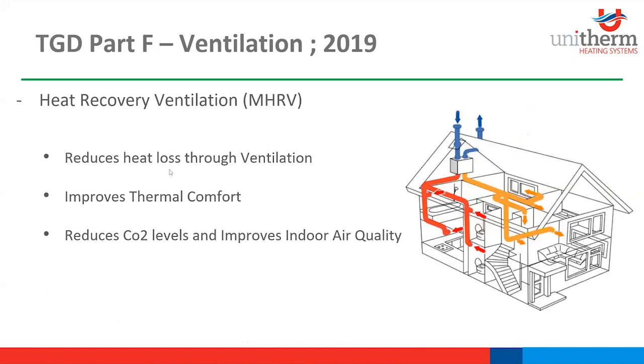So I suppose an example there, if you had warm air at 22 degrees in your kitchen, your bathrooms, your wet rooms, your utility, and cold air outside at 5 degrees, your air supply to your living rooms and bedrooms will be coming in around 18 degrees. So that's taken off the wind chill, or any kind of chill you have from dumping out warm air and bringing in cold air and putting more work on your heating system. So there's no compromise on thermal comfort there, as the fresh air is preheated through the heat exchanger before coming into the building envelope. Our systems as well use humidity sensors to boost the fans when a set point relative humidity level is reached. So you'll have nighttime running levels, daytime, but then there's also a boost level rather than boosting it on a switch. When we reach, say, 60% relative humidity, the machine will kick on and just bring that down to acceptable levels again of 45 to 55.